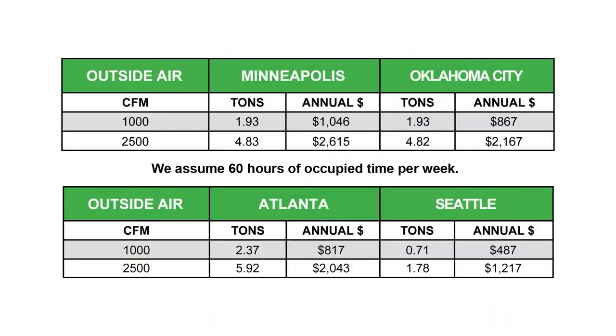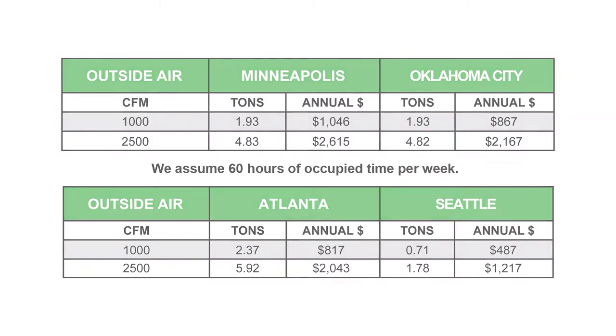We also have the patent-pending iAire IAQ logic, utilizing a CO2 and VOC sensor at the same time to reduce the amount of outside air brought into the space, reducing utility costs to the owner of the system. Looking at this chart, you can see several cities shown around the country. With each of these cities, you can see the potential tonnage reduction and ongoing average savings you can provide the owner. These savings provide a huge benefit to the users of our IAQ system over a standard economizer system.